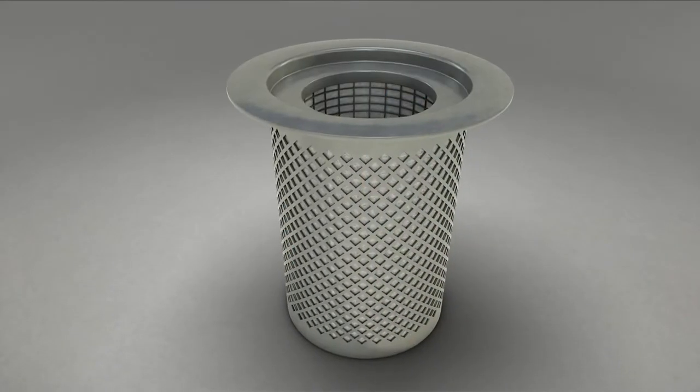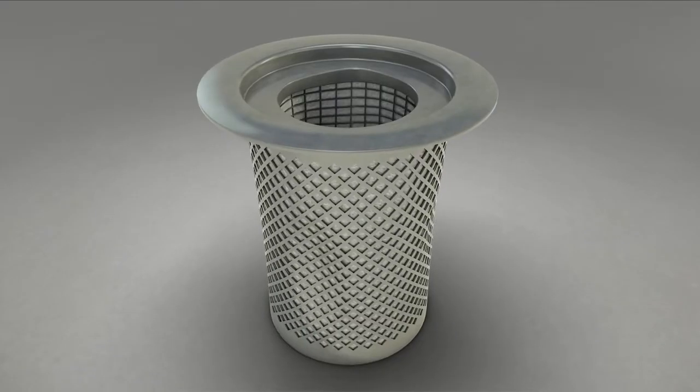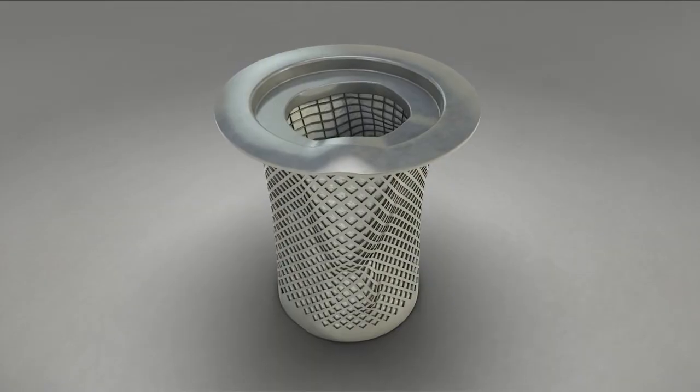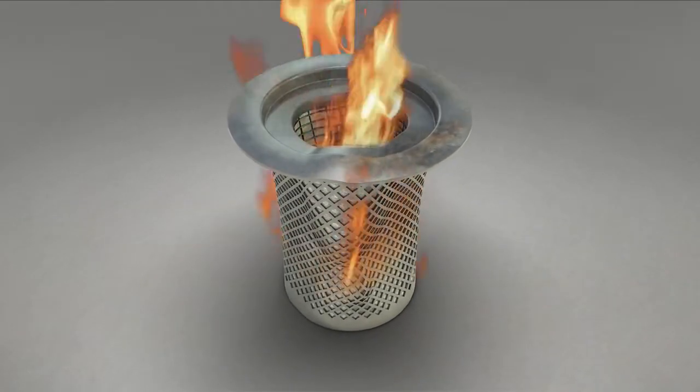In addition, there is the risk of a complete collapse of the air-oil separator due to increased pressure differential, or, if the element isn't suitably earthed, a fire caused by static discharge.